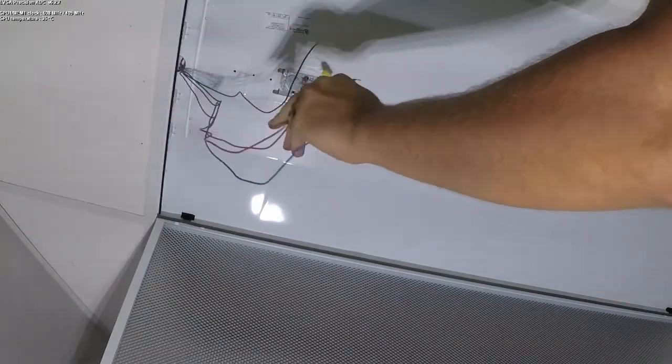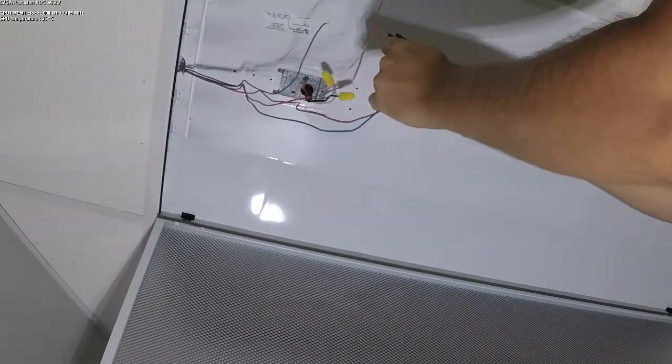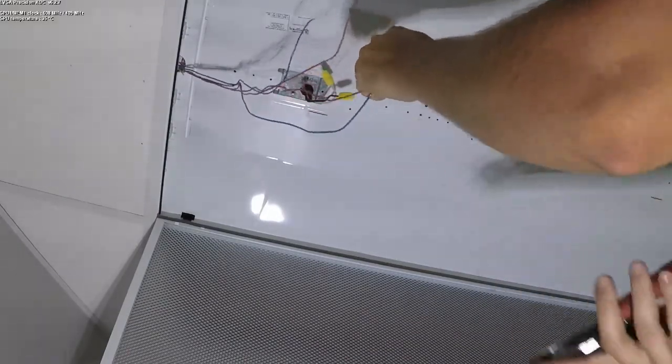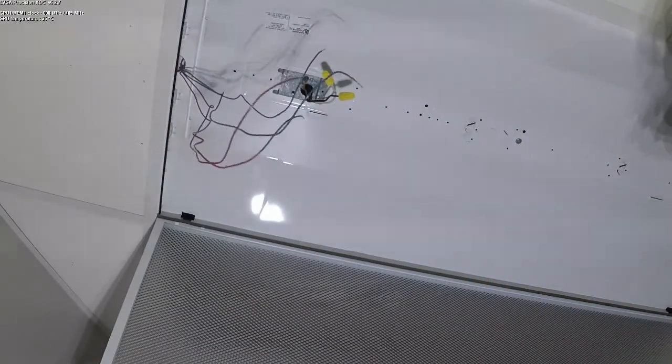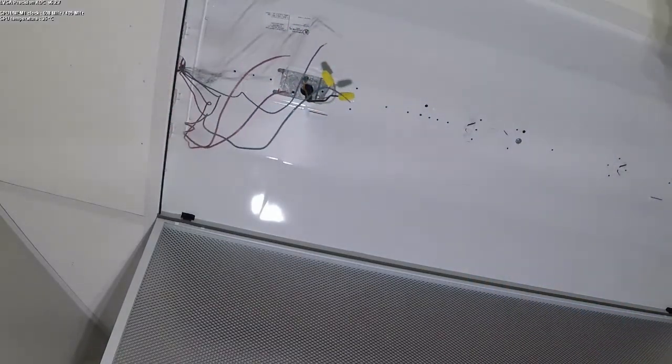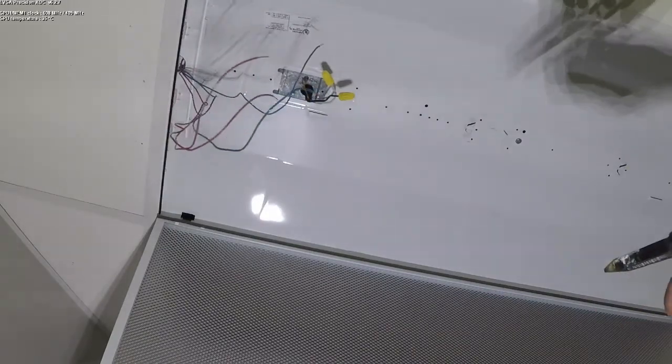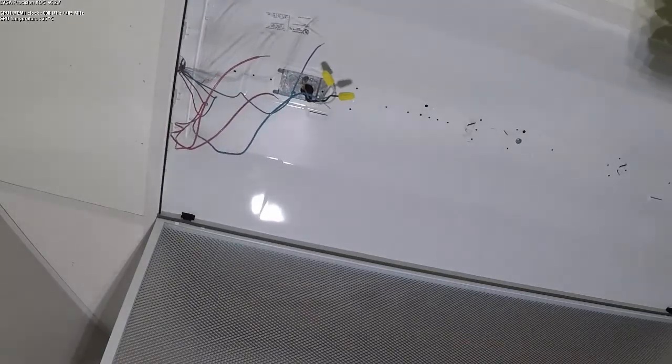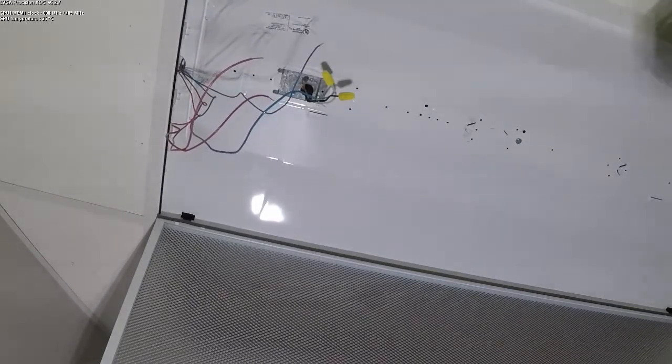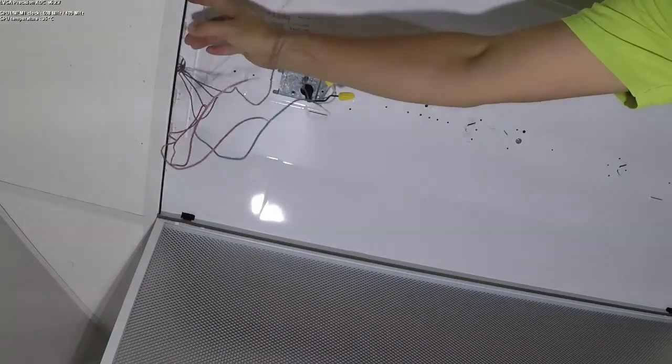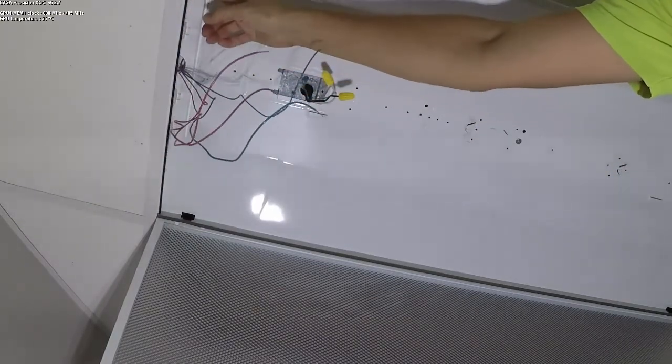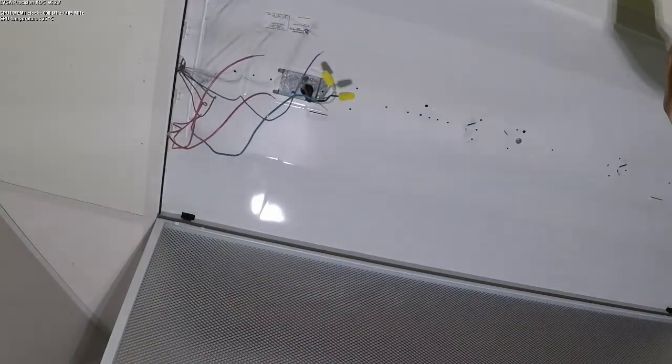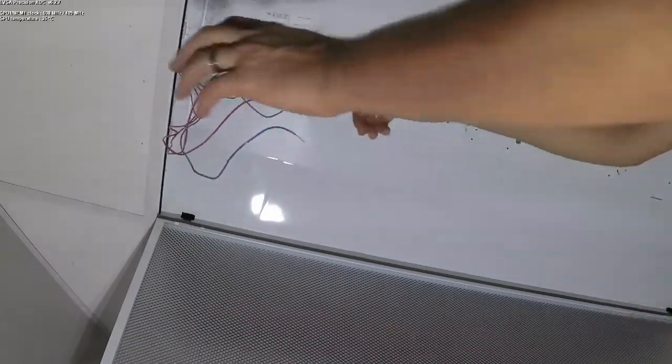And make sure you verify that your light fixtures are the same. You're not just taking my word for it. My ballasts have the wiring diagrams on them. You just got to power these bulbs with 120 volts. You don't need ballast anymore. They totally eliminate the ballast. So check the wiring diagram on your ballast and figure out how you can take the wiring that's there and make each tombstone, each lamp holder, have a hot and a neutral. Because you power these LED tubes from one end the way these are set up.